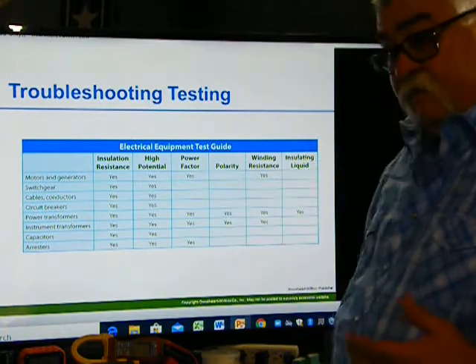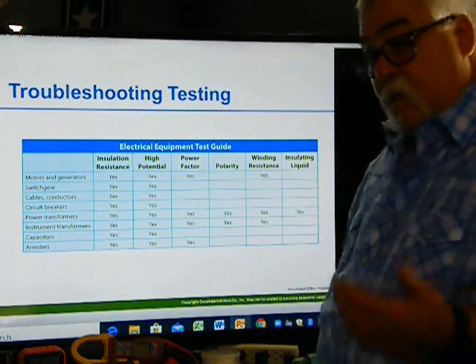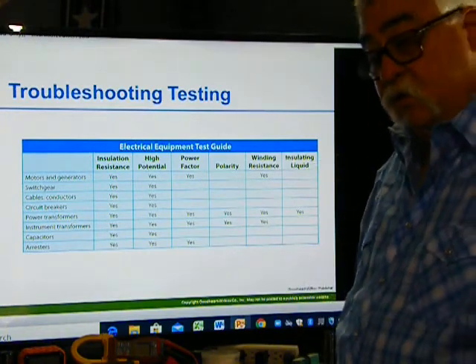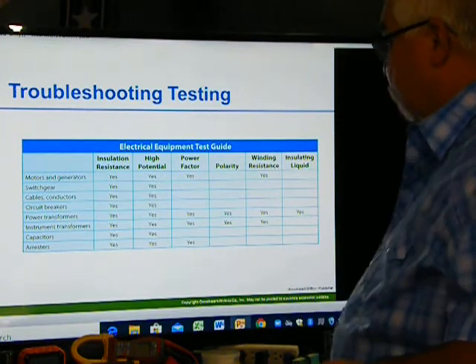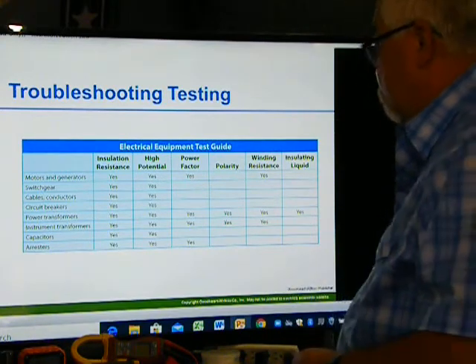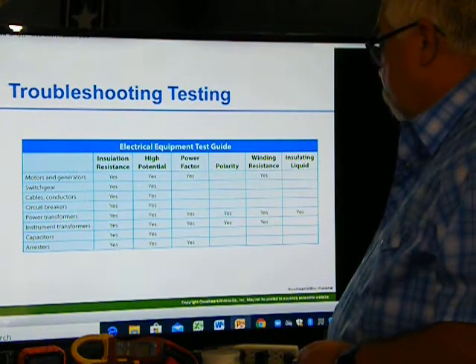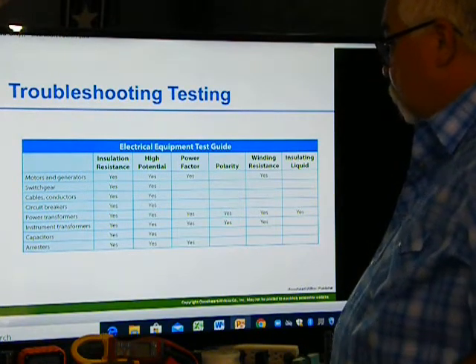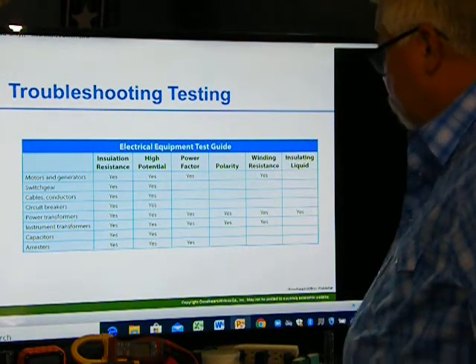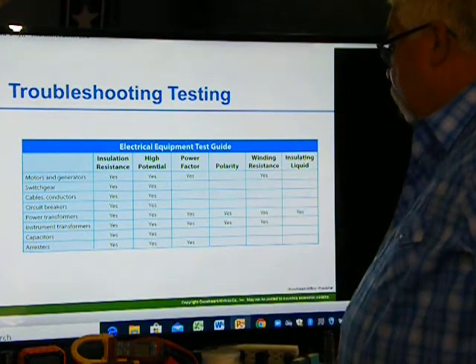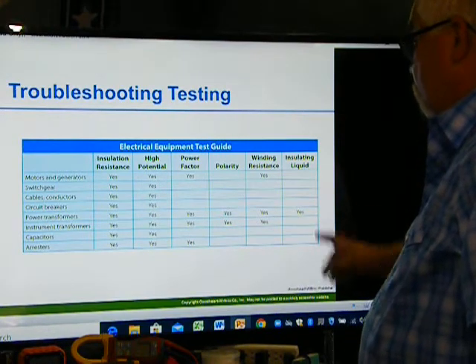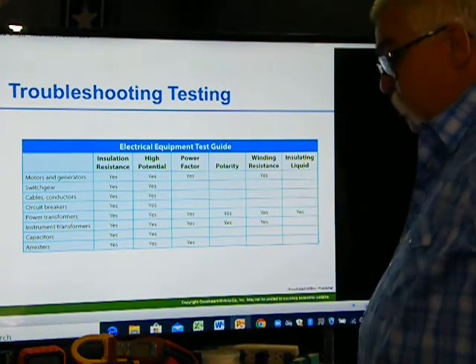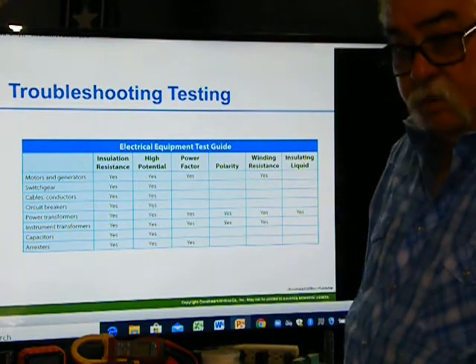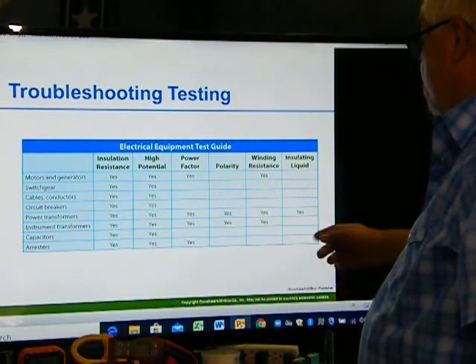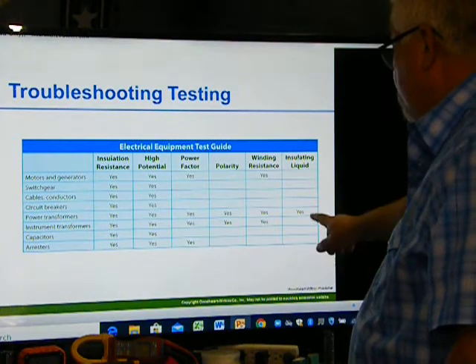So you want to make sure that the power factor is within a certain level. If the power factor is too low, you might want to put capacitors to increase your power factor. We will talk about the capacitors and power factor. Power transformers, instrument transformers, arrestors, polarity. Always check your polarity, make sure it's right. Your windings, yes, you check your windings. Make sure it's turning in the right direction. Make sure you don't have to put it backwards also. And then on the transformer, check your liquid.